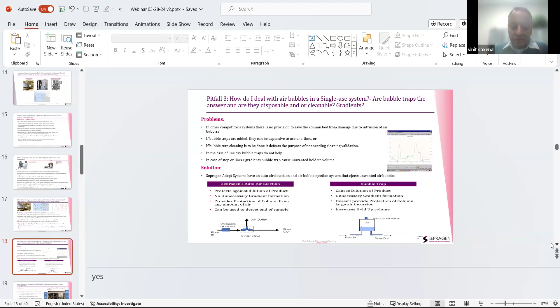And then what about leaks? Sometimes you have systems doing runs overnight, or unattended while the operator is doing other things. And with single-use systems, you've got lots of connections. You're running through a peristaltic pump, very often small peristaltic pumps. The tubing might wear out or get pinched. And if it gets pinched, you could have high pressure. You certainly can have high pressure alarms, and that'll trigger the system to stop. But what if there's a leak in the tubing or in the fitting? And usually you find that out too late because there's a big pool in front of your machine, or there's a loss of a batch.